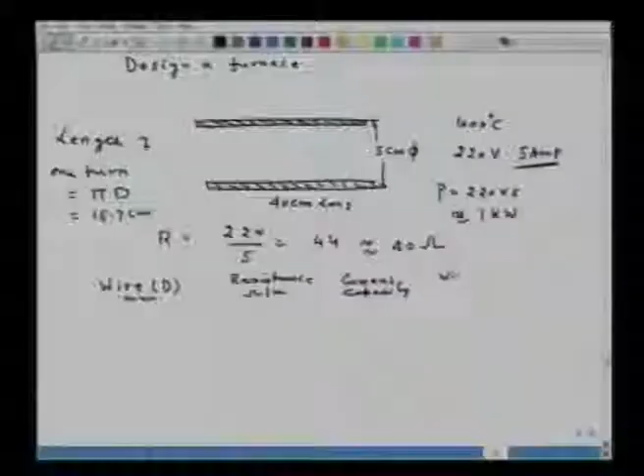So, I select the wire, for example, one is 1.60 millimeter. The resistance is given as 0.691, the current capacity is 10 ampere, that falls within my region of 5 ampere, and the wire length comes to, say, 40 divided by 0.691, that is 58 meter. If I use this wire, then I have to have approximately 369 windings on this particular tube, that is 5 centimeter diameter. That may not be possible.